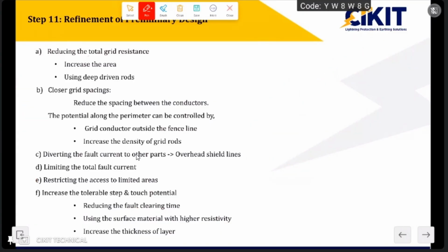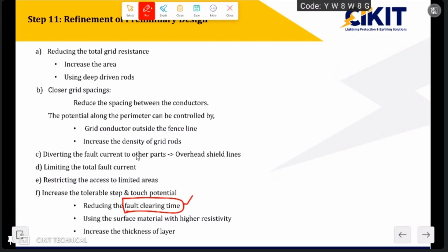If you closely observe, all the things we have mentioned mainly depend upon the fault duration. So if I reduce the fault clearing time, which means providing switchgear with very fast acting switches, then because of the fast operation, the fault clearing time will be reduced. So by reducing the fault clearing time, I can increase the tolerable step and touch voltages. Then, by using the surface material.